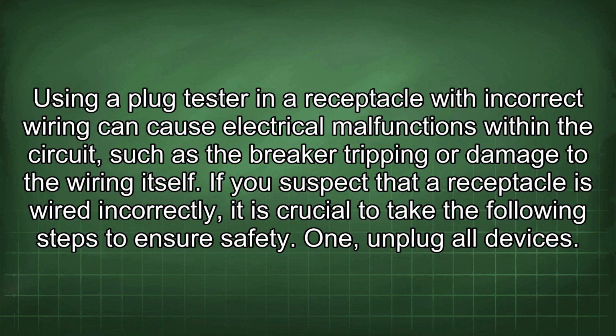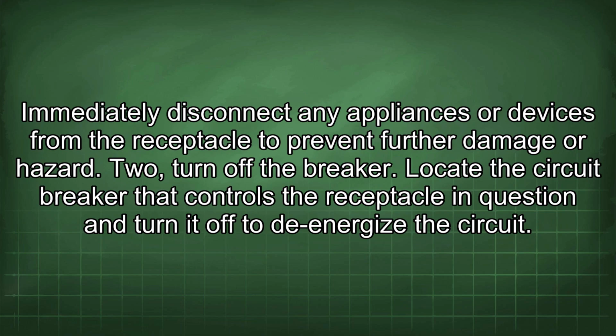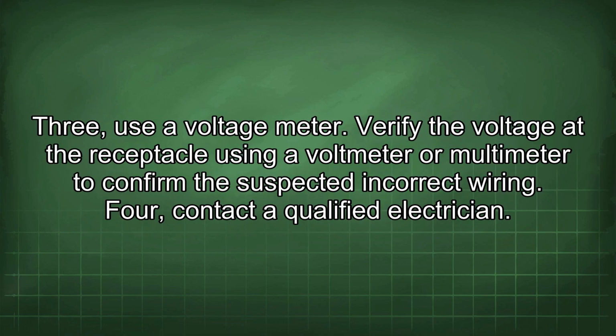If you suspect that a receptacle is wired incorrectly, it is crucial to take the following steps to ensure safety. 1. Unplug all devices. Immediately disconnect any appliances or devices from the receptacle to prevent further damage or hazard. 2. Turn off the breaker. Locate the circuit breaker that controls the receptacle in question and turn it off to de-energize the circuit. 3. Use a voltage meter. Verify the voltage of the receptacle using a voltmeter or multimeter to confirm the suspected incorrect wiring.